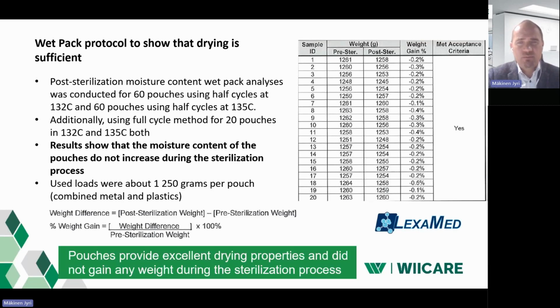So then we need to remember that there are materials in the marketplace which do not always provide dry packages, like some synthetic materials, for example. Then you might have water drops inside after the sterilization, which means that it's not sterile and they need to reprocess it again. Of course, it's fair to say that wet pack related issues are not only related to packaging, but of course the autoclave process needs to work, water quality needs to be good, vacuum pumps need to work, steam generators need to work, and pack assembly and all those things need to be in the right place, as you know. But this is a good study, really shows how excellently these materials perform.